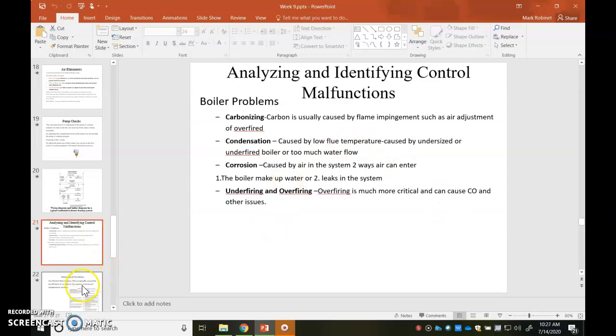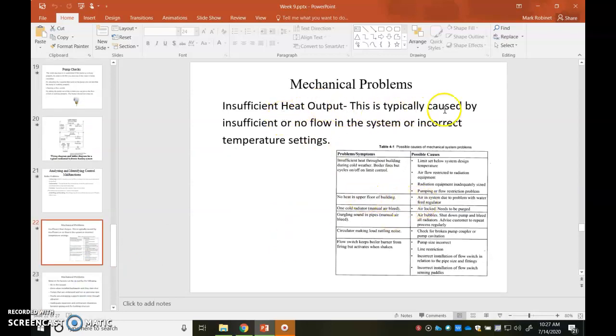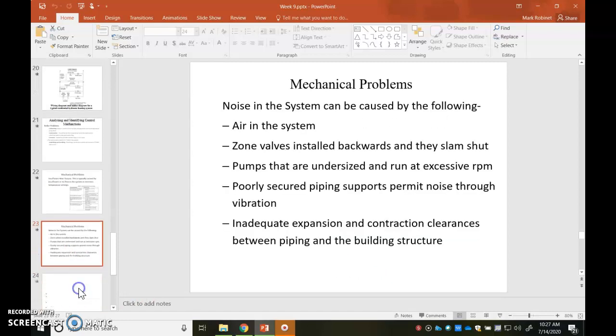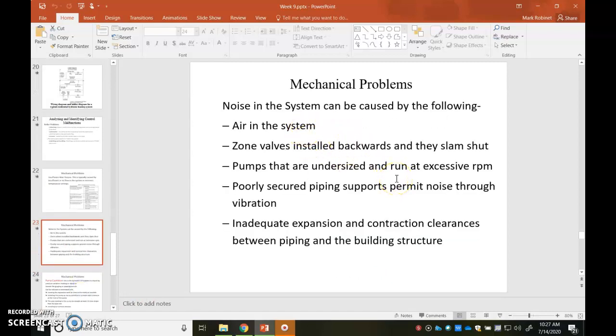Just a little bit. Mechanical problems, insufficient heat output, typically caused by insufficient or no flow in the system or incorrect temperature settings. So there's different things you can run into for why that is. Those are mechanical problems. Noise in the system can be caused by the following: air in the system, zone valves installed backwards, they slam shut. That's usually an initial installation thing. It's not something that you run into. It just does it on its own. Pumps that are undersized and run at excessive RPM will also cause noise.